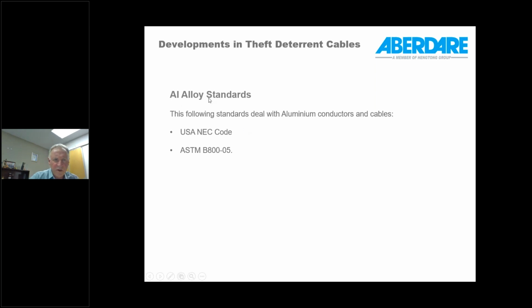So once again, the aluminium alloy standards are well documented in the ASTM standards, but the USA wiring code, so to speak, the NEC, also allows these small conductors to be used for wiring applications. And although the USA had very bad experiences in the earlier years with aluminium, it was with standard 1350 aluminium, where creep caused major problems for them, and many fires were caused through the use of standard aluminium for these small sizes.